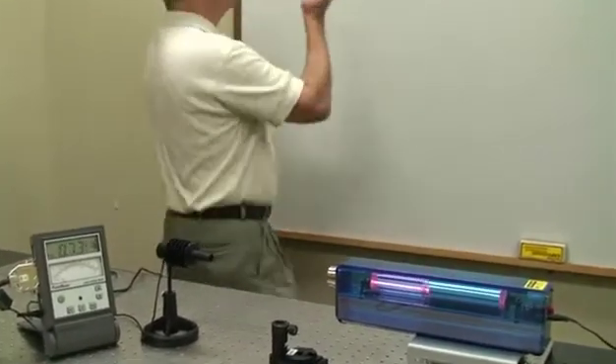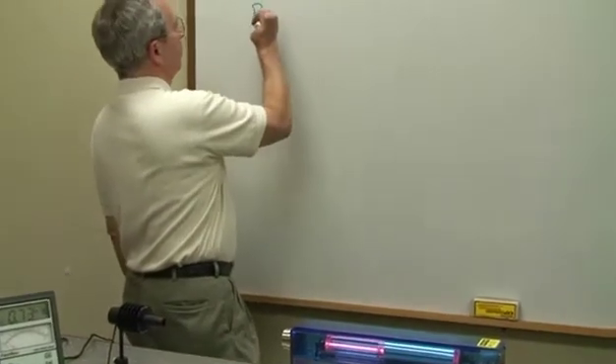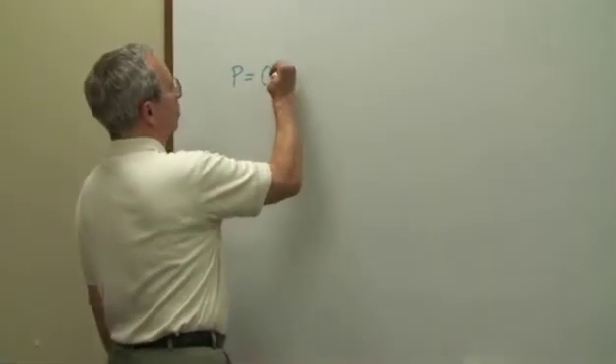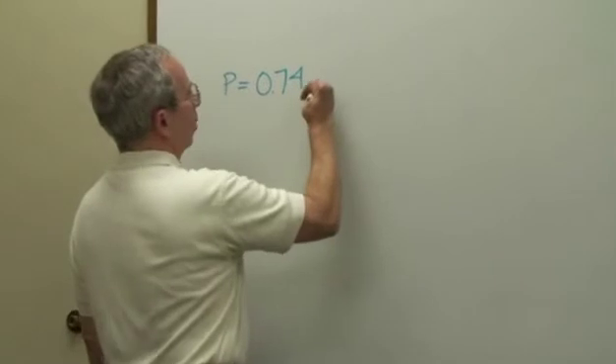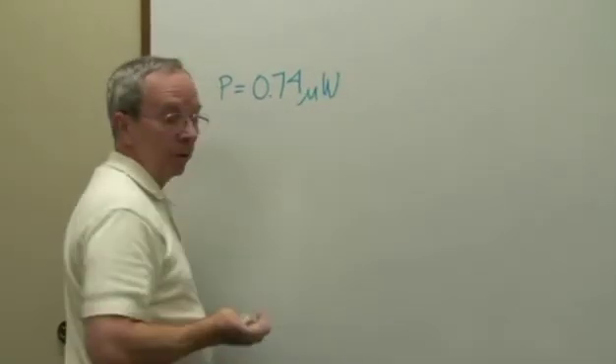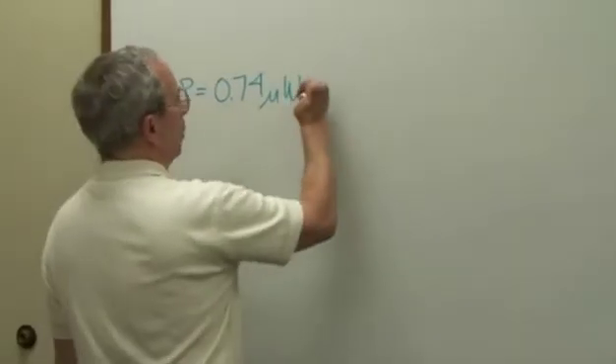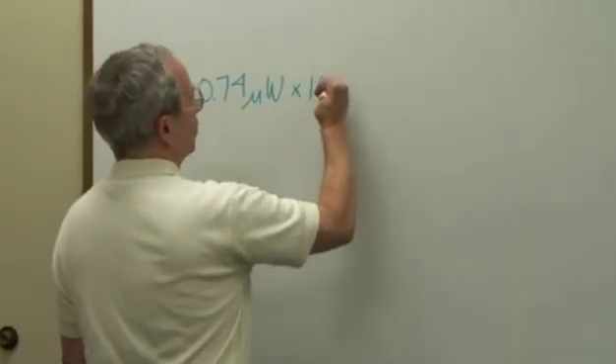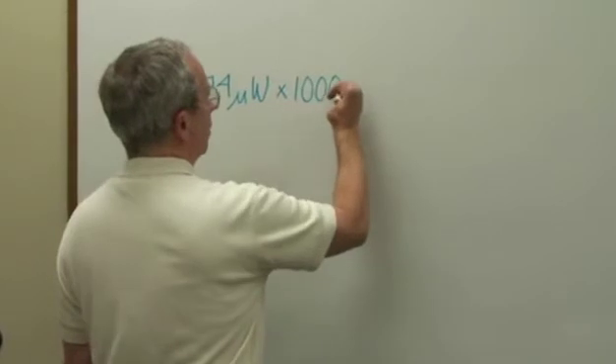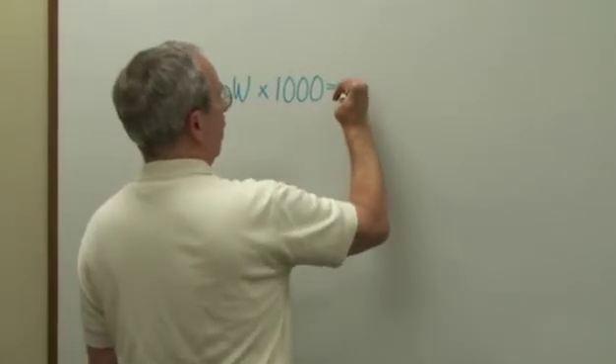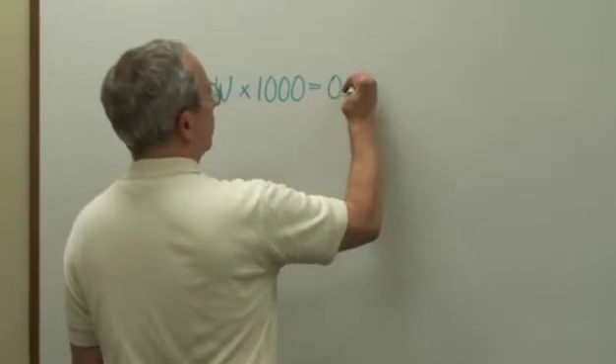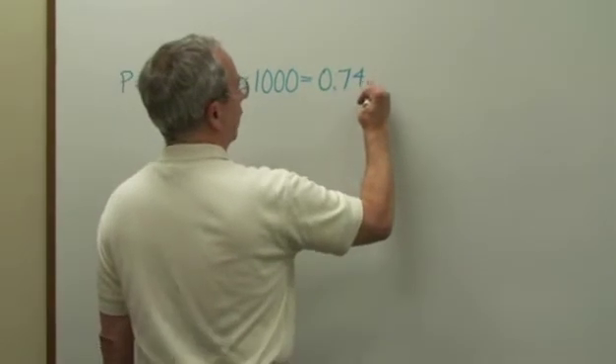On our data table, we'll record a power level of 0.74 microwatts. But remember that we're using a 1,000 to 1 attenuator here. So we're going to multiply this power by 1,000. And our actual power will then be 0.74 milliwatts.